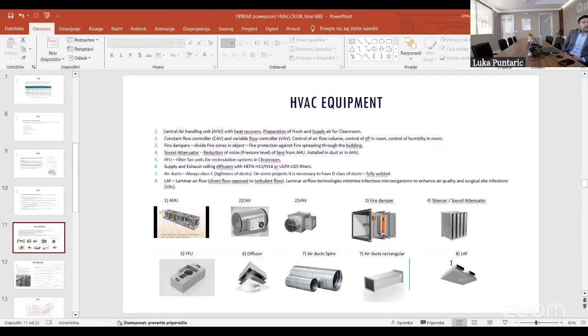We have sound attenuators, silencers, on picture number 4, with which we reduce the noise pressure level of the fans from the air handling unit. They can be installed in the air handling unit itself or in a duct network before the air enters the room. Then we have FFU units, fan filter units. Those elements are for recirculating the air, which we showed before.